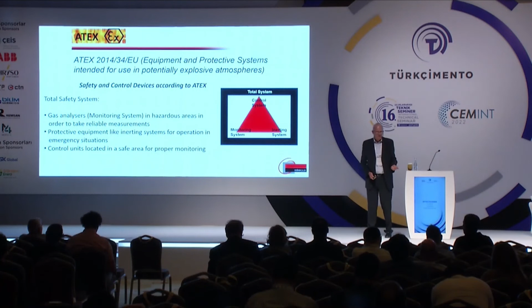The next one, of course, is ATEX. ATEX is applied for all equipment in terms of monitoring, analysis, etc. All equipment in contact with explosive atmospheres needs to be ATEX certified. The total safety system is a description that comes from the ATEX directive, and it comprises the gas analyzer as a monitoring system, the protective equipment in the form of an inerting system—that might be nitrogen or carbon dioxide—and in addition, certain control units in order to monitor and control the entire system. This is the meaning of a total system under ATEX.